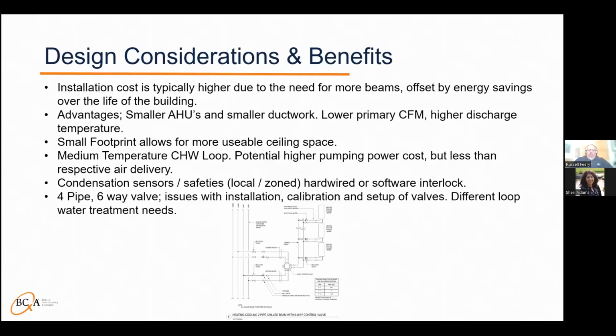The projects that we've worked on have also been 4-pipe. One of the most recent ones is a 6-way valve configuration. That's the project that we're working on right now, and it has proven to be challenging, not only for the installing contractors, the mechanical contractors, from a piping standpoint, getting it right, but also the setup and calibration of the valves has been challenging for the control contractor. And because they do share common return lines, although for a brief moment in time, there are different water treatment needs between the two loops. So I would recommend against a 6-way valve setup based on our experience that we've seen recently.